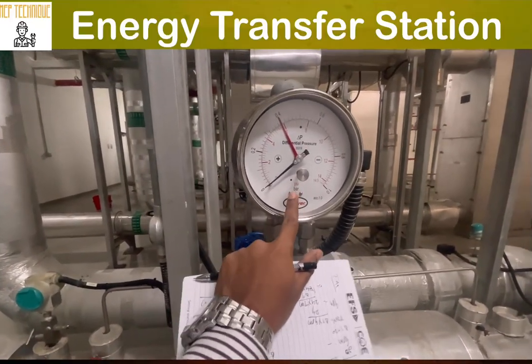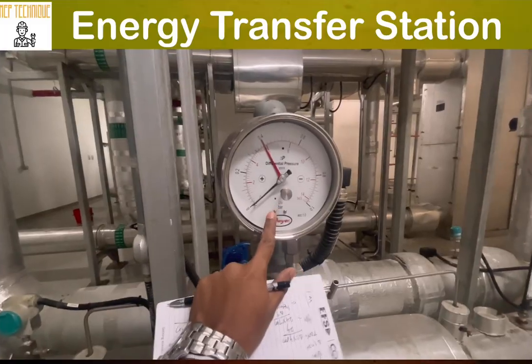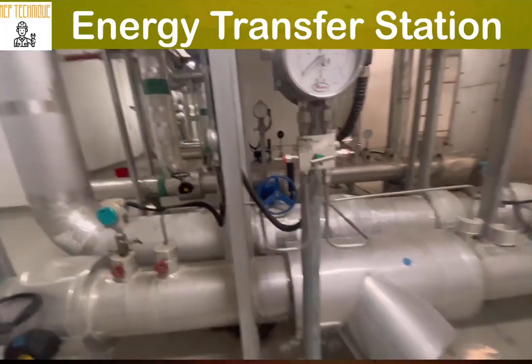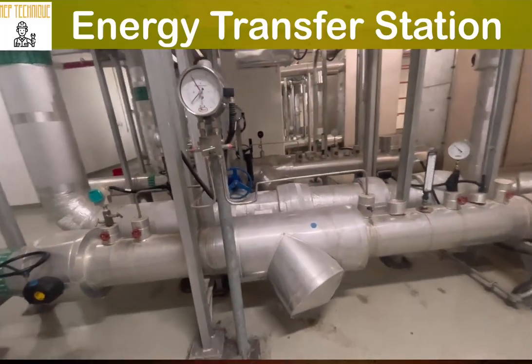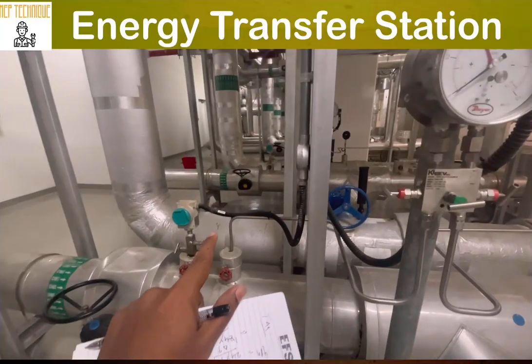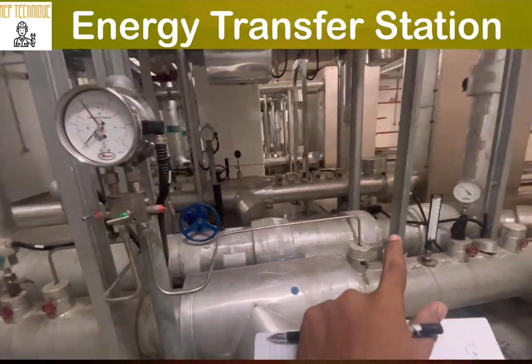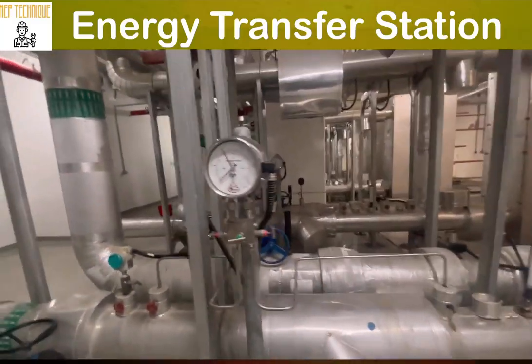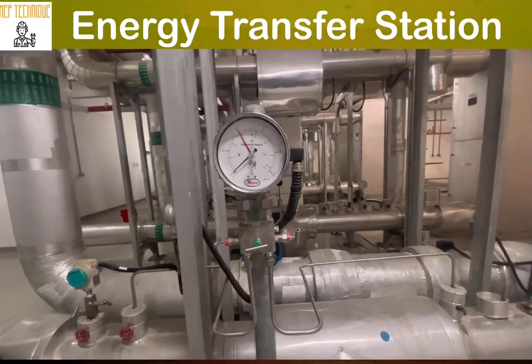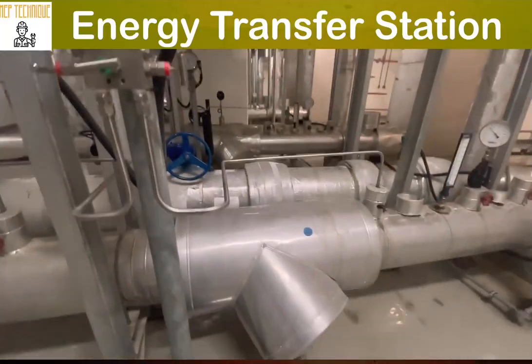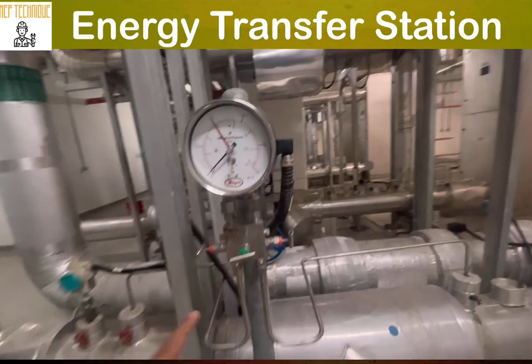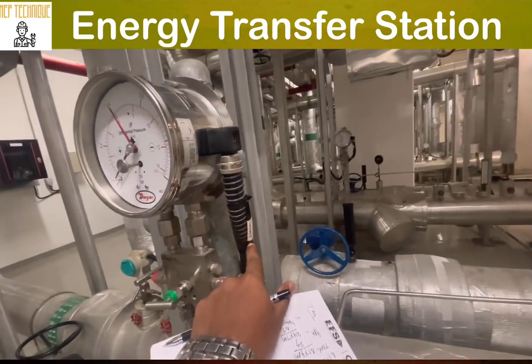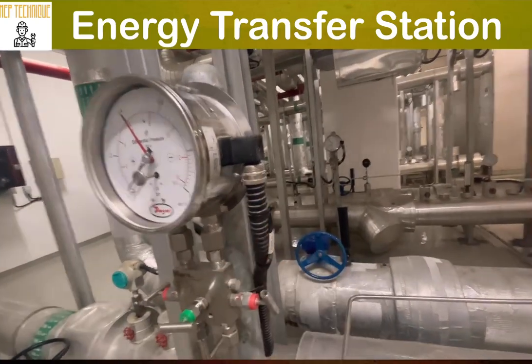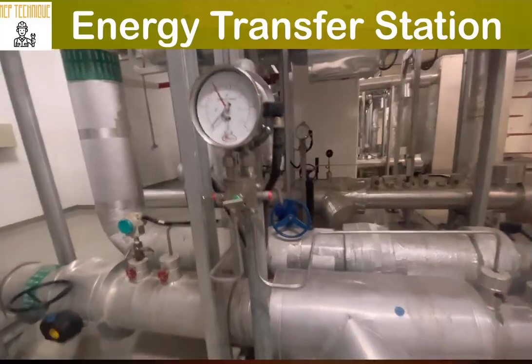So what is the purpose of this differential pressure gauge? You can see this DPG connected across the strainer. One connection is here, and another one is here. Both are connected with the DPG to monitor the differential pressure across the strainer. If it increases, it is integrated with our DDC panel, and through the DDC panel we will be notified.